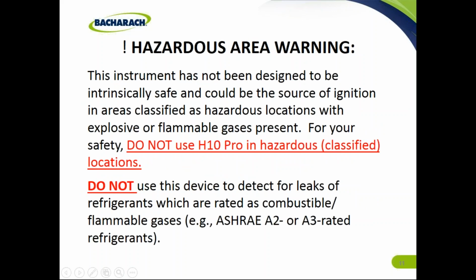The instrument has not been designed to be intrinsically safe, and could be the source of an ignition in areas classified as hazardous locations with explosive or flammable gases present. For your safety, do not use the H10 Pro in hazardous classified locations. Do not use this device to detect leaks of refrigerants which are rated as combustible flammable gases, for example, ASHRAE A2 or A3 rated refrigerants.